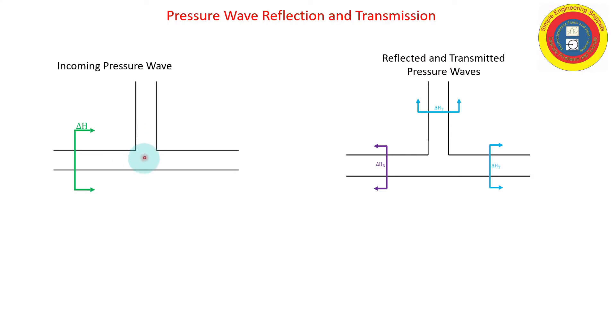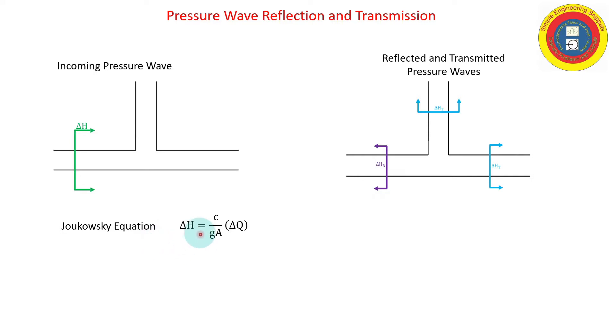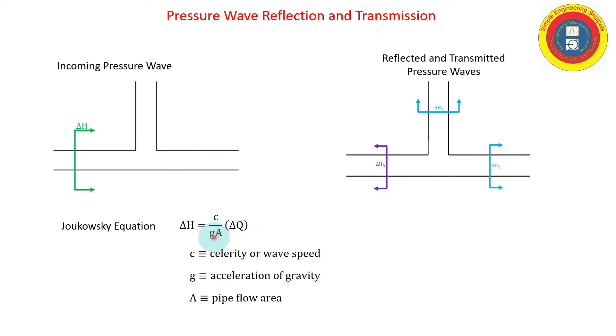Here's the situation for a three-pipe junction: I have an incoming wave denoted as delta-h that interacts with this three-pipe junction. There will be transmitted waves in the downstream pipes and a reflective wave in the pipe with the incident wave. The basis for this is the Joukowski equation, which tells us that the head increase due to a change in flow is equal to the change in flow times the celerity divided by the acceleration of gravity and the pipe area. The grouping of celerity divided by gravitational acceleration accounts for the compressibility of the liquid and the elasticity of the pipe.